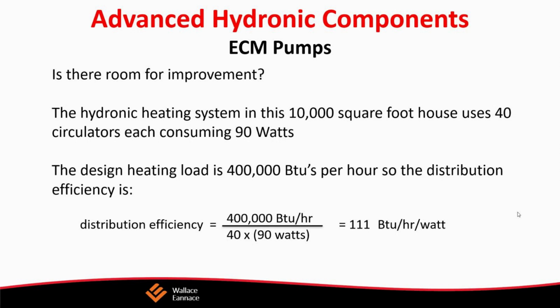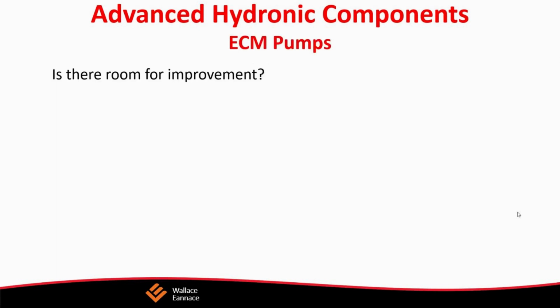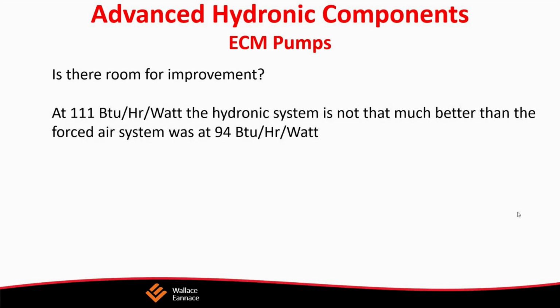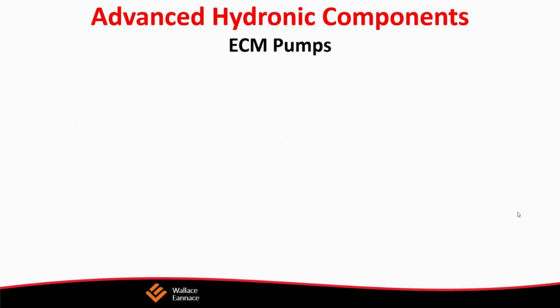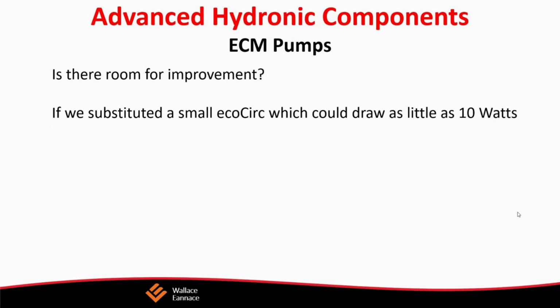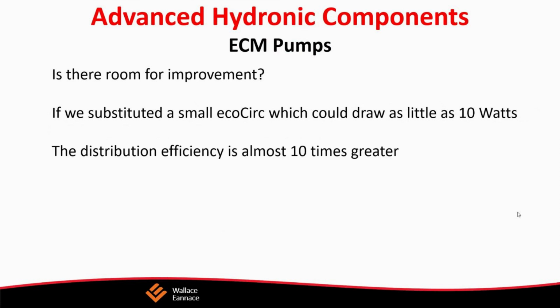So is 353 BTU per hour per watt good or bad? We need to compare it to something. So let's take a look at a furnace blower, which operates at 850 watts and delivers 80,000 BTUs, which is typical for a furnace blower. Thus, its delivery efficiency would be 80,000 divided by 850 watts, or about 94 BTUs per hour per watt.